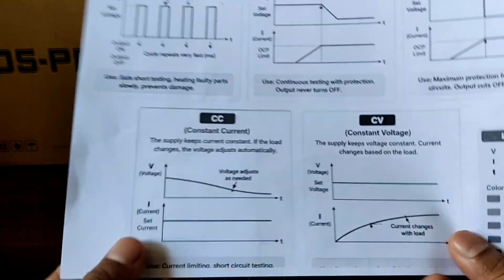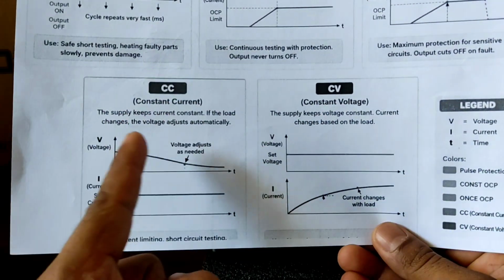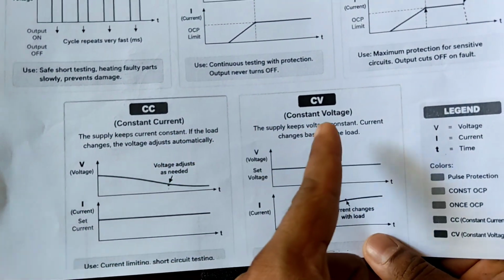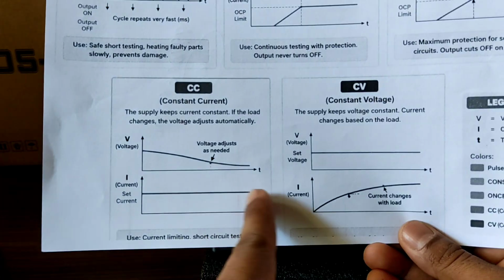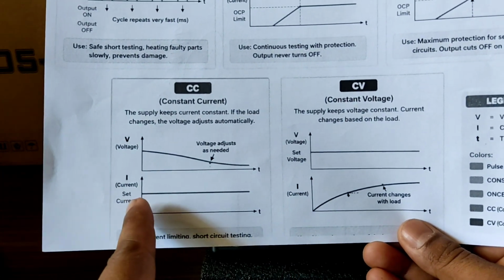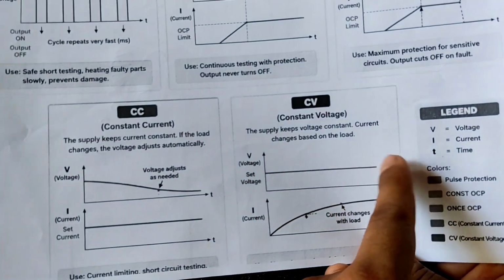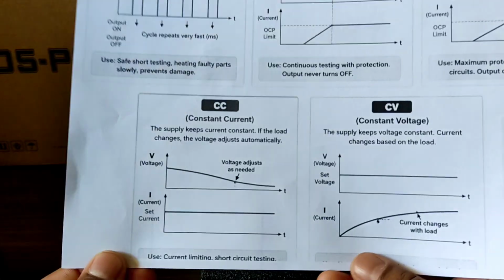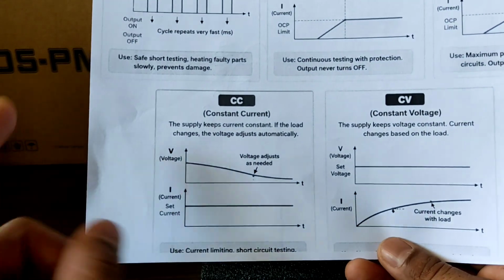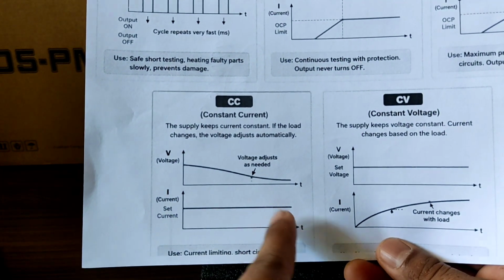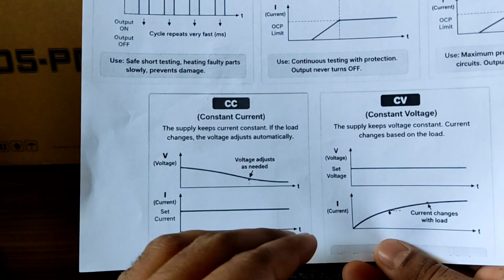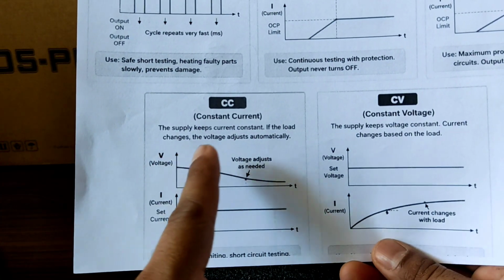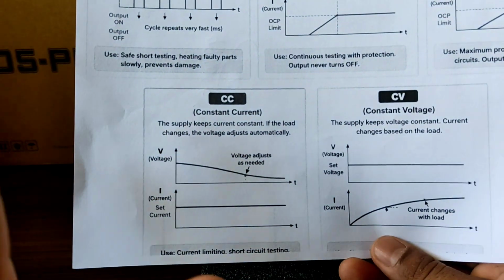CC and CV - see this graph. CC means constant current, CV means constant voltage. In CC mode, the current will be constant throughout the output. In CV mode, the voltage will be constant throughout the output. Whenever a short or fault occurs in CC mode, current stays constant and voltage will drop or adjust according to need. The supply keeps current constant. If the load changes, the voltage will adjust automatically.